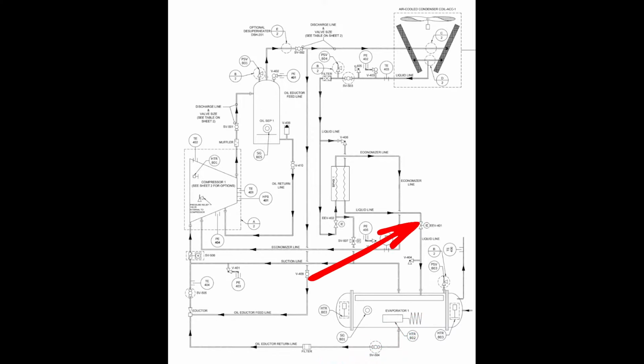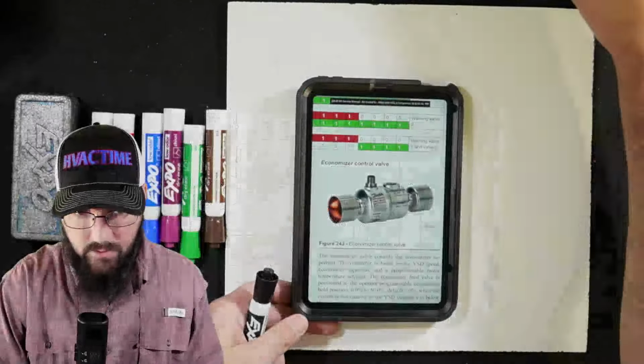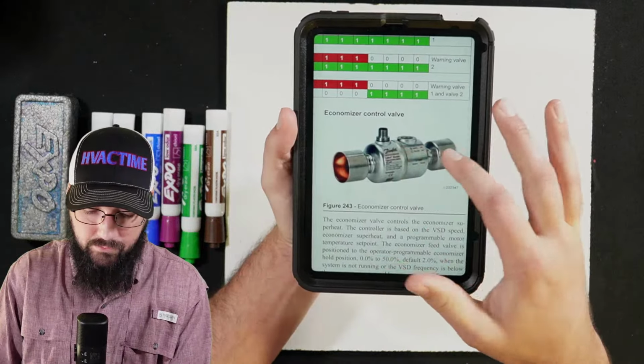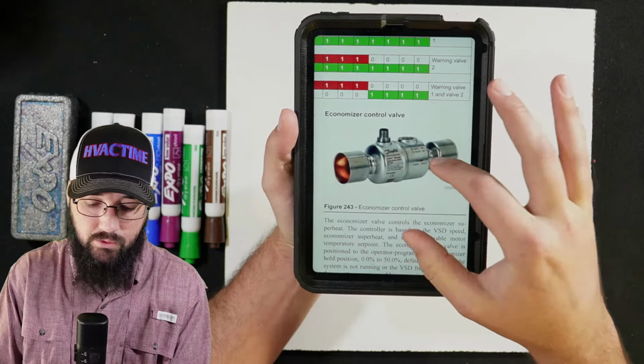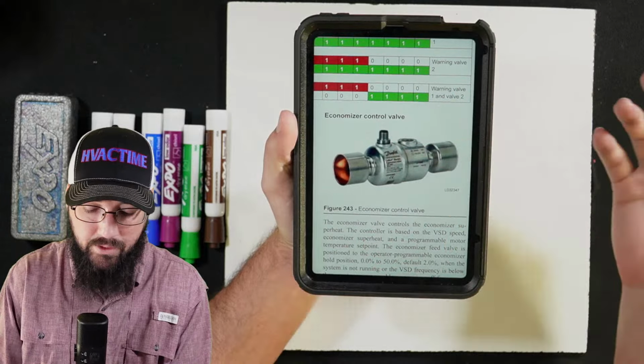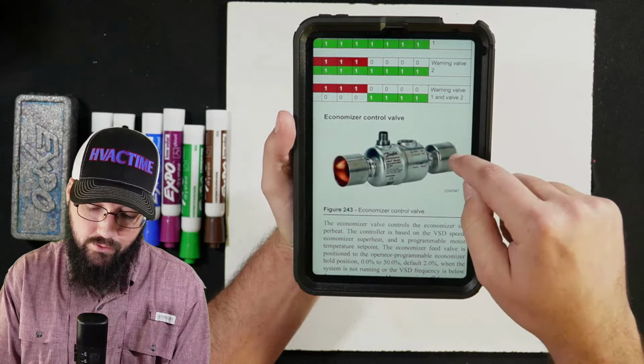So one primary EXV feeding to the evaporator, and then we do have another EXV actually down here. So this line right here, this is our economizer line. This would be a T coming off of the main liquid line, feeding into a little small EXV. This EXV is what feeds the cooling circuit of the economizer line. All right, and I can show you what that EXV looks like. Got it pulled up here. So they show it's a Danfoss, so it's just a little small valve. That's where your wiring would connect to, but it's still doing superheat control on this machine. So this would be the EXV.